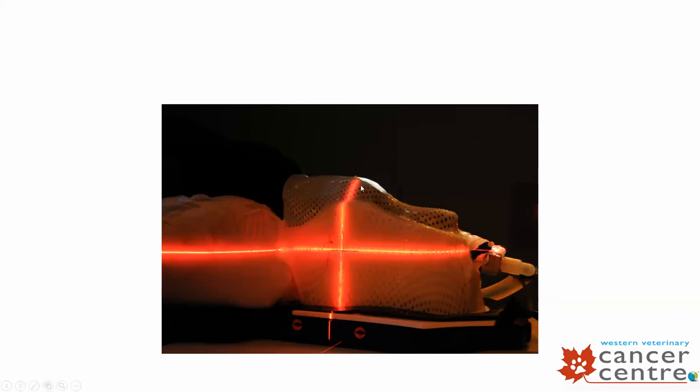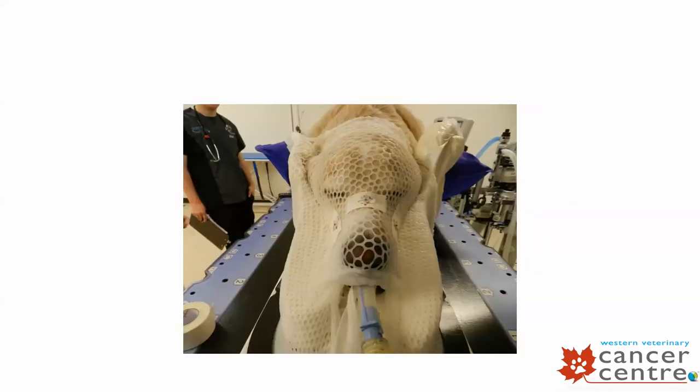There are lasers in the radiation vault and lasers in CAT scan. These are aligned similarly so that they identify a sort of virtual point in space, something that's called isocenter. And isocenter is the point in space that the linear accelerator is going to rotate around. So we define that point down in the linear accelerator vault, we confirm that point up in the CAT scan, and then hopefully between those two, using the laser alignment, the position our patient is in down in the vault will be exactly the same position that he's in up in CAT scan.